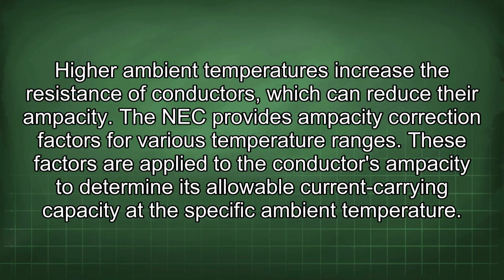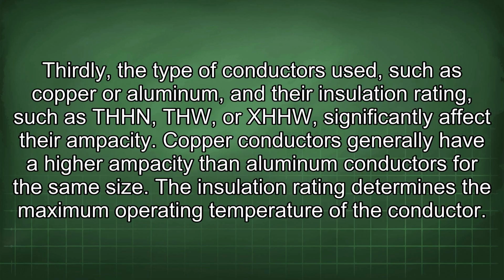The NEC provides ampacity correction factors for various temperature ranges. These factors are applied to the conductor's ampacity to determine its allowable current carrying capacity at the specific ambient temperature. Thirdly, the type of conductors used, such as copper or aluminum, and their insulation rating, such as THHN, THW, or XHHW, significantly affect their ampacity. Copper conductors generally have a higher ampacity than aluminum conductors for the same size. The insulation rating determines the maximum operating temperature of the conductor.